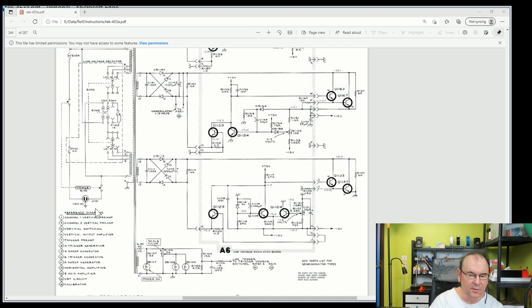So anyway, as I was saying, the user manual actually contains some circuit diagrams. So I was actually able to check the power supply input and the plug. And thankfully they've actually drawn it here. They were showing that it was actually grounded. So I could double confirm that this instrument was intended to be run grounded. And that led to me checking why the ground was missing. Since obviously the chassis wasn't grounded. But anyway, that's fixed now. It's still running. And there's no sign of smoke or anything.